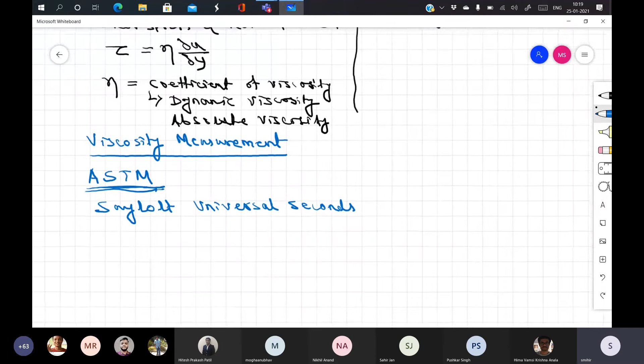So what happens here? There is a container, the volume of the container is defined by ASTM, and at the bottom there will be an orifice. Now you put a specific amount of lubricant as per the marking in the container, and container size, volume and dimension are fixed by ASTM. Now different kinds of fluid you put there and measure the timing, how much time it requires to completely vacate the container. The container has an orifice at the bottom, so liquid will come out of that orifice, and you measure how much time it takes. That time is called the Saybolt universal second.